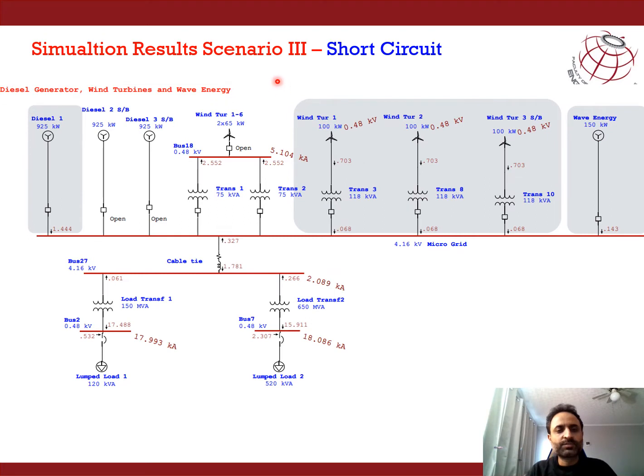For scenario 3, if we talk about short circuit levels, you can see the three sources are now pumping fault current into the system. The total fault current is now increased to 2.089 kiloampere. On the secondary side at the load bus, this is increased to a maximum of 18 kiloampere. But still this is within the limit of 25 kiloampere, so we were able to converge the results for the short circuit studies and keep them within the limits in scenario 3 also.